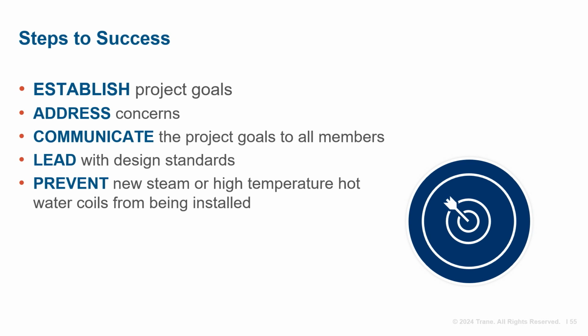For large buildings and campuses, the first step is often to establish design standards that align with decarbonization or electrification goals, if that's important to the owner. These standards should, at a minimum, establish design criteria for lower temperature hot water coils and prevent new steam or high temperature hot water coils from being installed in new buildings and discourage them in existing building renovations.